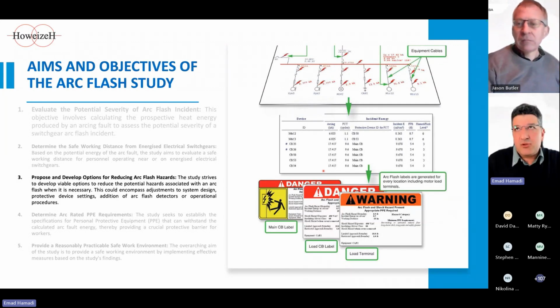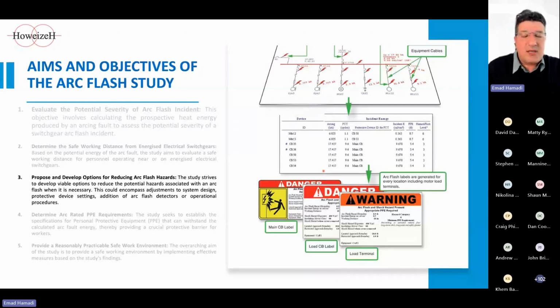But don't forget, the protection settings have other priorities as well. I mean, the protection grading study is done in a way to mitigate the risk, yes, but also to minimize the system disruption. Normally the grading of the protection setting is such that it waits for the closest relay to the incident to trip first, and it has a time delay. You can just set all the settings in the network to instantaneous tripping and put them at the lowest settings, and you are on the safe side from the arc flash perspective. But then you end up with a system that is very sensitive to faults, and any fault downstream can lead to a blackout.